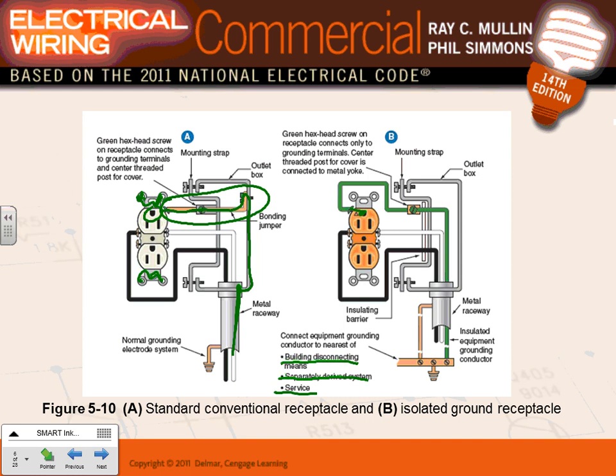If this is an isolated ground receptacle, you know what they do? They take a conductor from this slot that grounds only this slot, not the frame, the slot. Take it through this panel. They don't land it here. They take it through this panel, all the way up through that service, and the ground takes that green conductor all the way to the service.